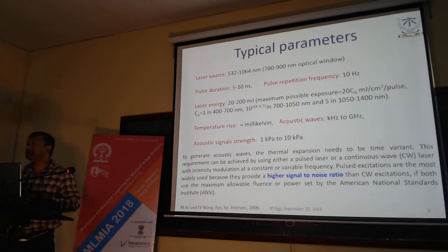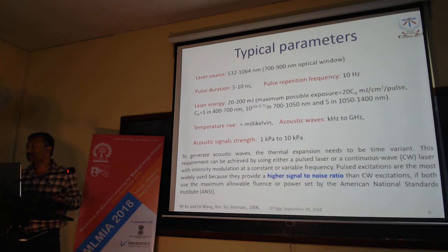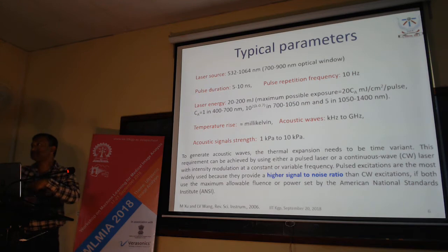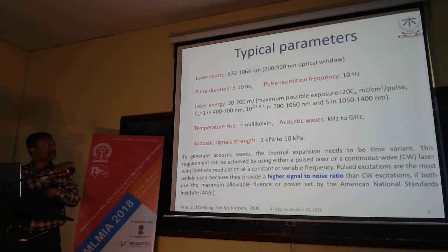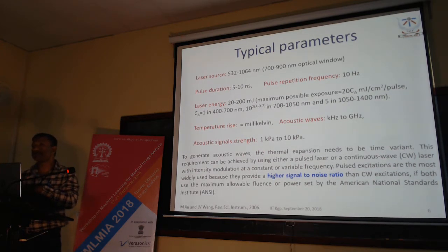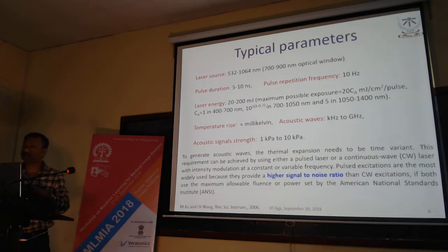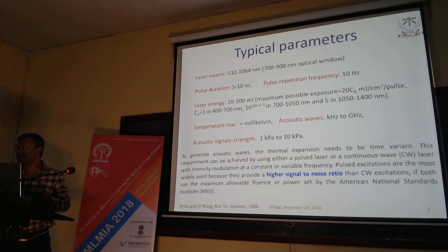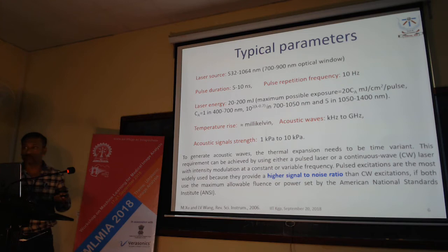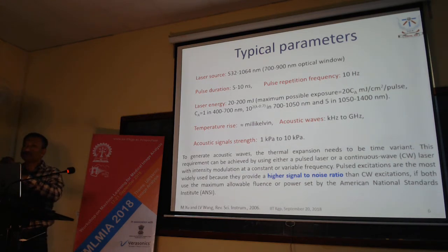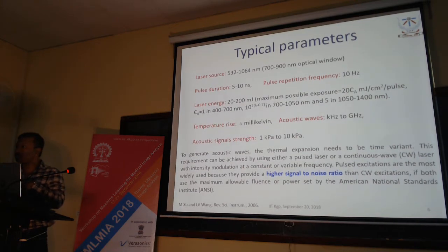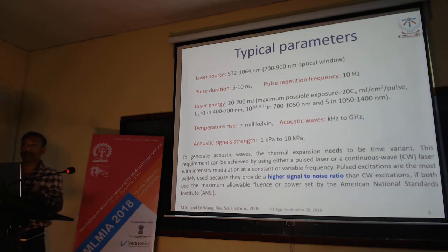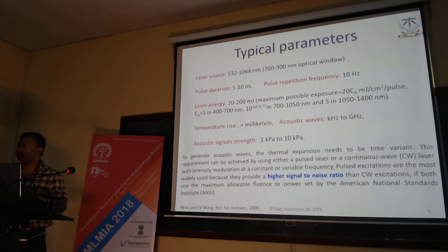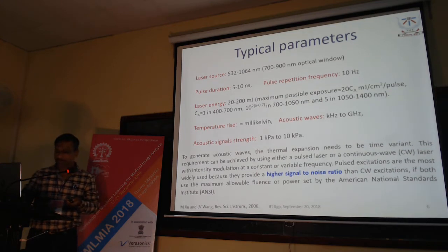Many times people ask me why we use a nanosecond laser to generate photoacoustic signals. For example, some light is coming and illuminating our tissue. According to this effect, we are still producing photoacoustic signals. Yes, in this process also our tissue is generating photoacoustic signals, but the problem is that the SNR, signal to noise ratio, is not high. But when you use a pulsed laser to suddenly illuminate a tissue within a very small time window, it will produce signals with a much larger signal to noise ratio. So it will be detectable and useful for many groups.